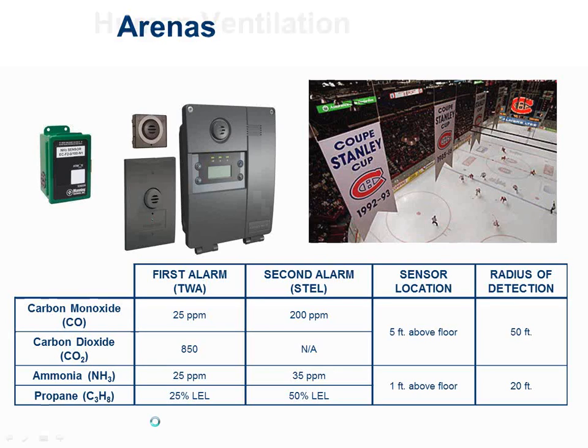For human ventilation, typically I'm looking at carbon dioxide. As I mentioned, carbon dioxide is not a deadly thing. It is just something I want to use as a surrogate to see if there are people in the room or not. If there are less people in the room than the code design number of people, I can modulate your ventilation air back. If your space required 1,000 CFM of outside air and less people show up to work today, I can throttle your ventilation air back if I can use CO2 to measure the amount of people in there.